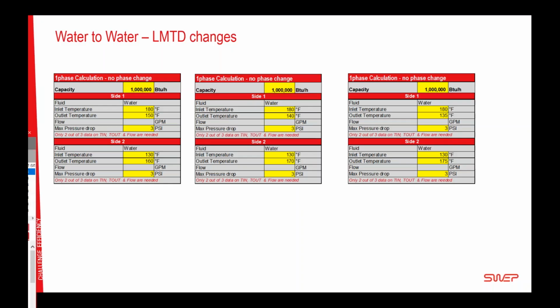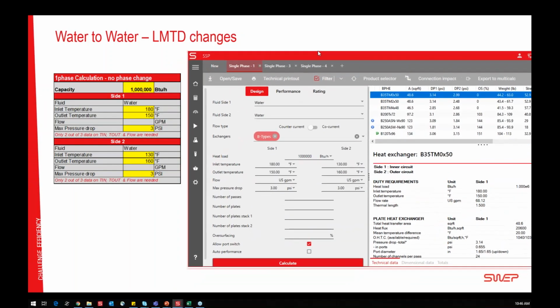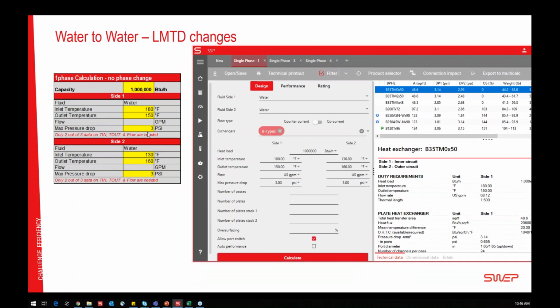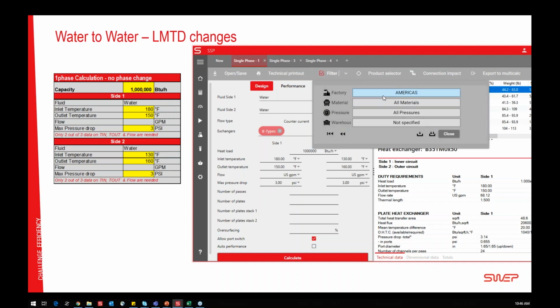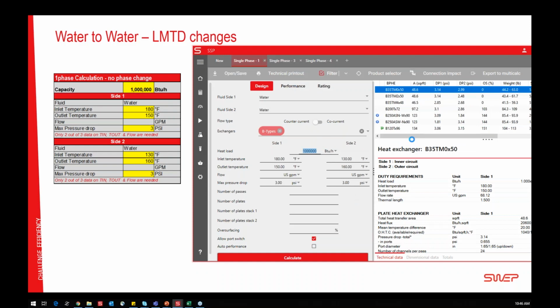I have actually prepared a little bit in advance here to make it smoother. So with 1 million BTUs, I've entered 1 million here. Temperature is 180 to 150 on the hot side, you see there. 130 to 160, that's there. And then maximum pressure drop 3 psi on both sides. What I also did was go to the filter, and I chose the factory of Americas because I wanted it made close to me to have this 3-week lead time.